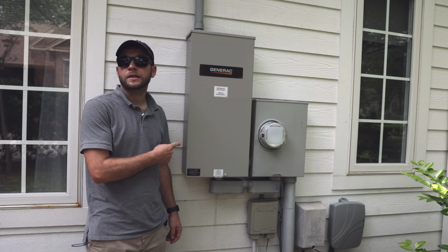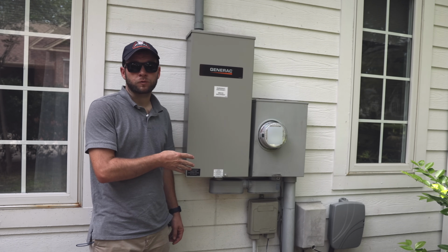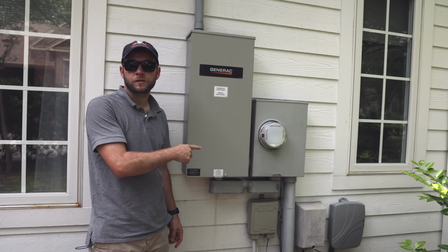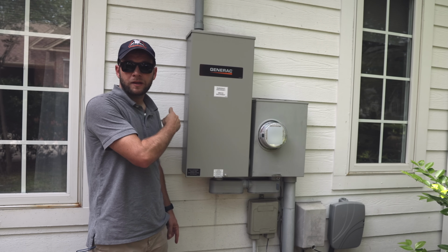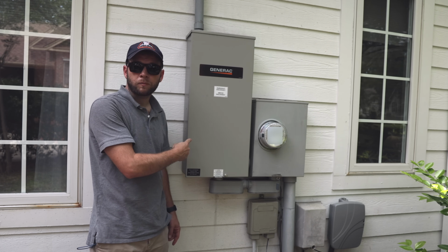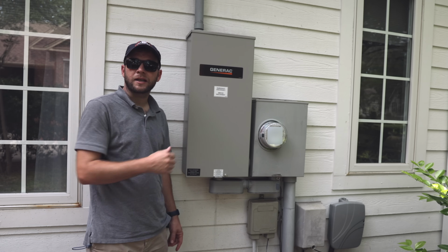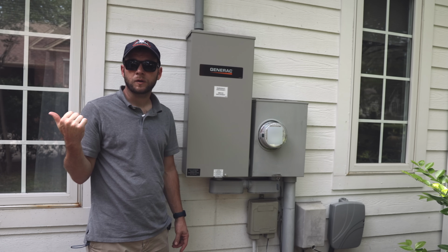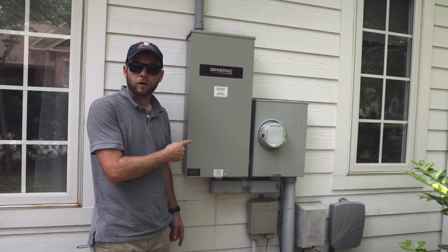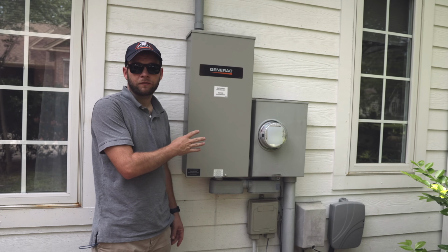Now, beside me right here is the automatic transfer switch, or ATS. This is a service-rated automatic transfer switch, so this is actually between the main meter coming from the street and the transformer, and in between the power panel on the inside of the house. Whereas normally you would go from your meter into your panel, you're now going through this disconnect, and this disconnect is connected to the generator full-time and has a relay and contactor in here with a bunch of monitoring hardware, and that is on the main service entrance side of the unit.